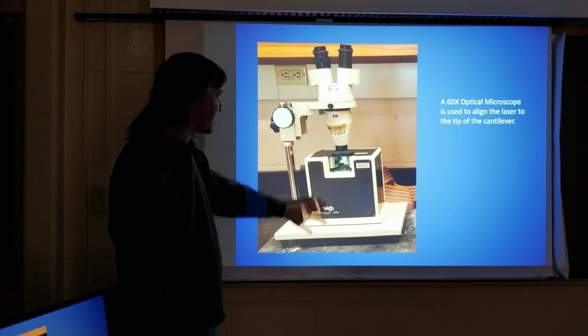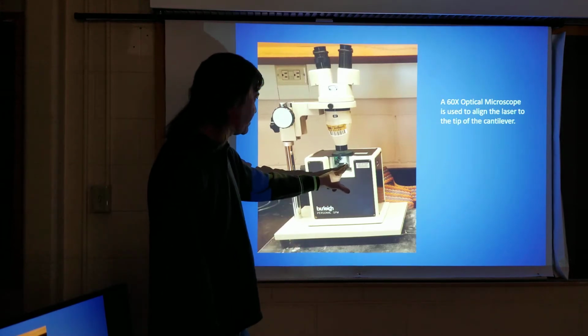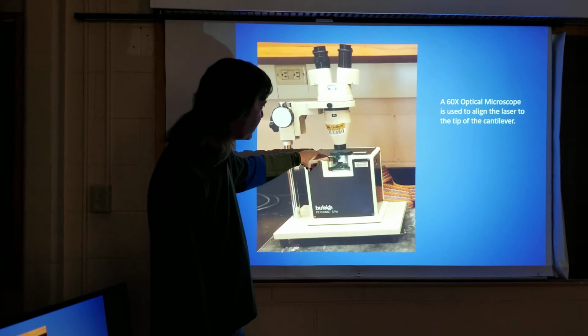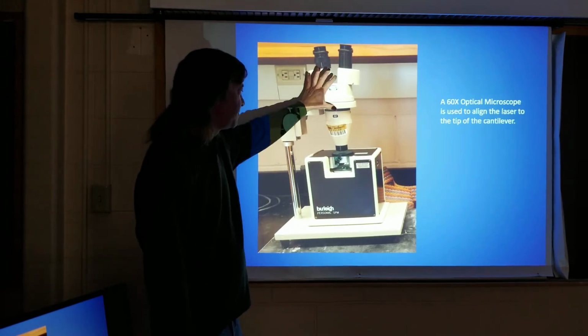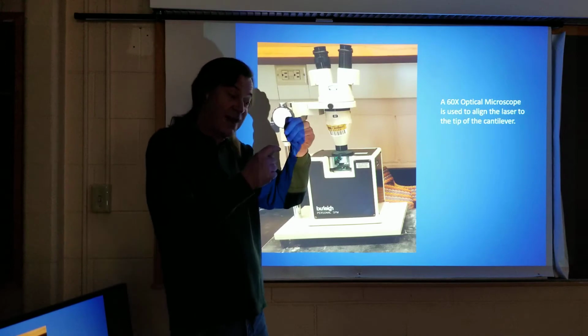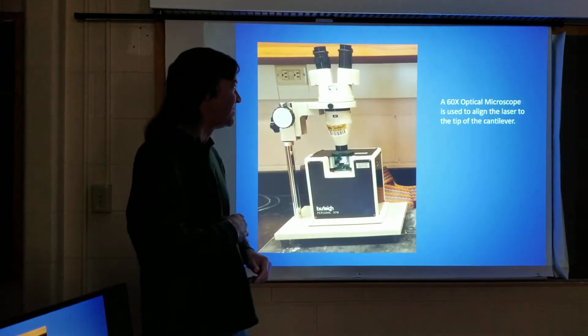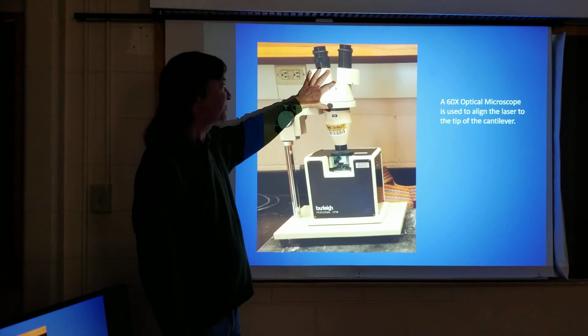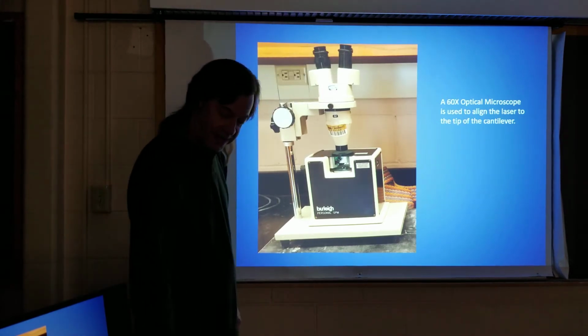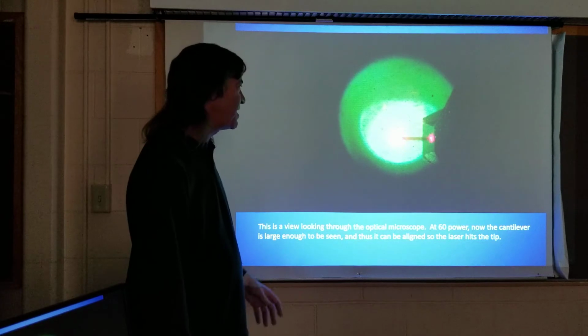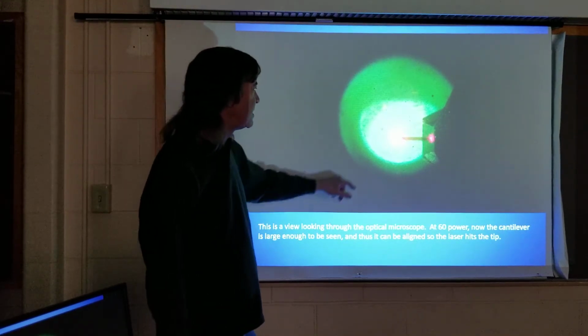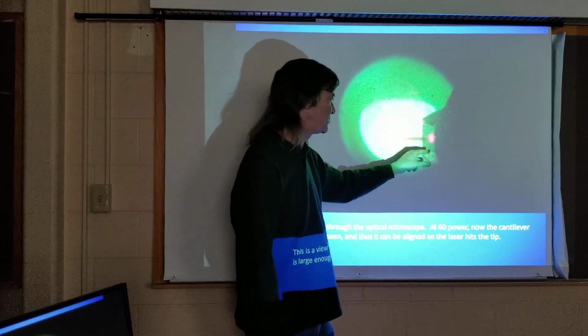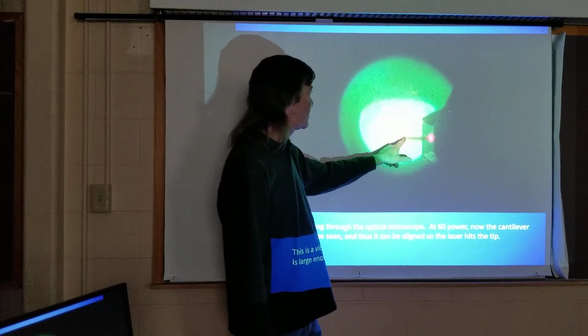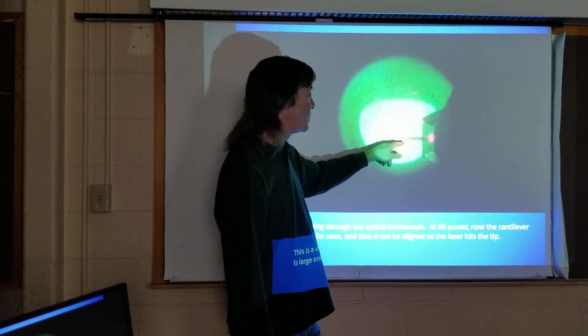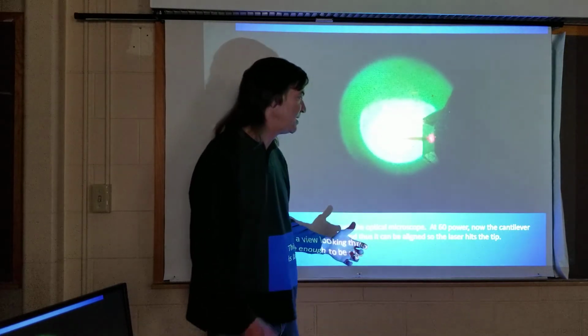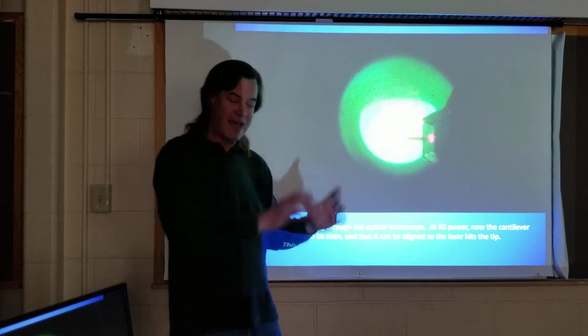This shows, again, here's the AFM. There's where the laser is, the tip is right there. There's my detector, this round guy. The sample would just go right in here. But when we're trying to align the laser onto the tip of the cantilever, it's so small that we need a nice optical microscope. This is a 60 power. We can look right through it, and this is what it looks like from the optical microscope. You can see there's that big holder, which really is small. And then there's the cantilever, and there's the laser hitting the tip. So we know we have it aligned. Once we have it aligned, we need to make sure the detector is moved around to capture it as best as possible.